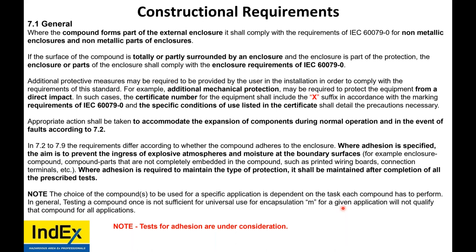Now, additional protection methods may be required. For example, additional mechanical protection. But where it is required, it may be required where there's a risk of direct impact. In such cases, the certificate number shall have the X, conditions of use, listed in the certificate. So you don't refer to this standard. You refer to the certificate and the IOMs.